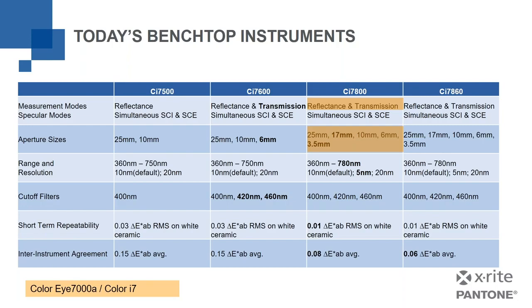The aperture sizes for those previous instruments is the same as the 7800. Their range, however, and their resolution is in that lower section, 360 to 750. And the resolution to a maximum, or minimum, I should say, of 10 nanometers, where now we can go to 5 nanometers in the 7800 and the 7860. Those devices had a single cutoff filter. Again, needing different cutoff filters, what they do is they're cutting off the UV light below 400 or 420 or 460 nanometers. The reason you might need those is for some very specific optical brightening agents. Fluorescent substances may require that you use that. Short-term repeatability for those instruments was 0.01, and their inter-instrument agreement was 0.08. So you can see the differences there. There are others as well that we'll talk more about as we keep going here.